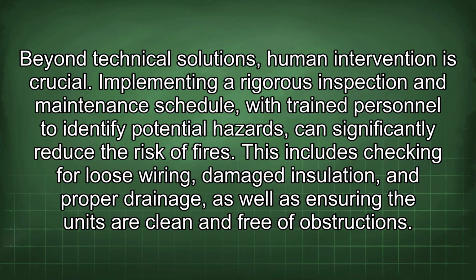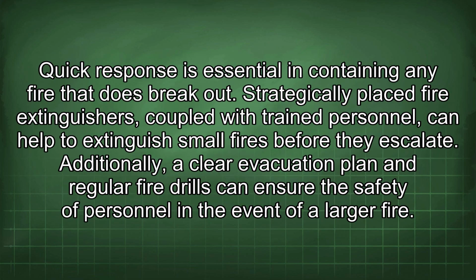Beyond technical solutions, human intervention is crucial. Implementing a rigorous inspection and maintenance schedule with trained personnel to identify potential hazards can significantly reduce the risk of fires. This includes checking for loose wiring, damaged insulation, and proper drainage, as well as ensuring the units are clean and free of obstructions. Quick response is essential in containing any fire that does break out. Strategically placed fire extinguishers, coupled with trained personnel, can help to extinguish small fires before they escalate. Additionally, a clear evacuation plan and regular fire drills can ensure the safety of personnel in the event of a larger fire.